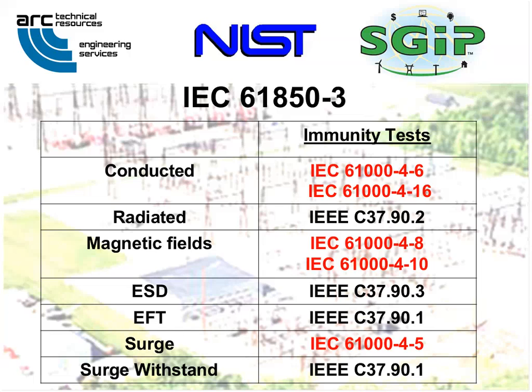61000-4-3, radiated fields, to IEEE C37.90.2, which already existed here in the U.S., so it wasn't a gap. I should point out here that we require a higher level of testing for radiated RF immunity under the IEEE 1613 pair: 20 volts per meter rather than 10 volts per meter. And we include pulse modulation up to 6 gigahertz, which is not included in the IEC version.